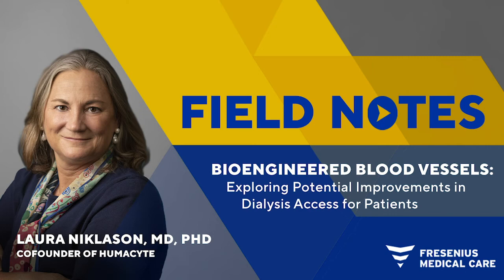Right now, the HAV is not yet cleared by the FDA but is in the phase three trial. What is the process left between now and commercializing a product? We have a number of phase three trials underway in dialysis access, and we're in the process of converting a vascular trauma trial into a phase three trial. Once those trials are completed and we have the data readout, we would submit that data to the FDA as part of a Biological Licensing Application, or BLA. The BLA includes the clinical data, but also a tremendous amount of data around our manufacturing process, the stability of the product, and a lot of laboratory investigations. After the FDA reviews that BLA application, hopefully they'll issue an approval.